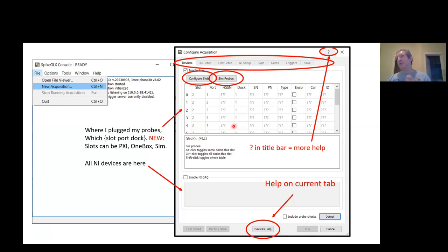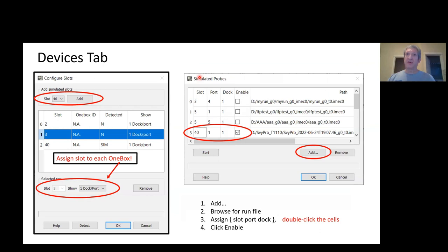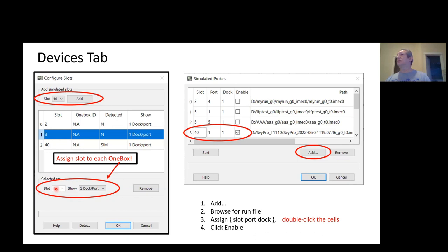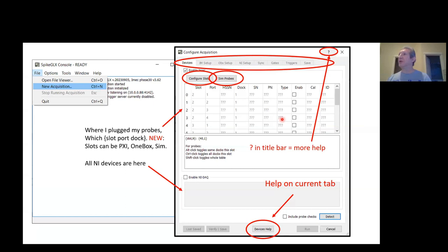We need to give it a slot so that it will show up in this table. Also, we've given you the ability now in SpikeGLX relatively recently to have virtual slots so that you can run the software without having any real hardware. So in order to do those things, there's now a configure slots button that opens up a dialog. You're going to see the hardware that you've enabled, the hardware that you have connected. You want your OneBox turned on for this. You'll see it in the list. Click on your OneBox and you can assign it a slot number. Now it will show up in that table. You can pick a slot number, click Add, and add simulated devices into your list of hardware here.